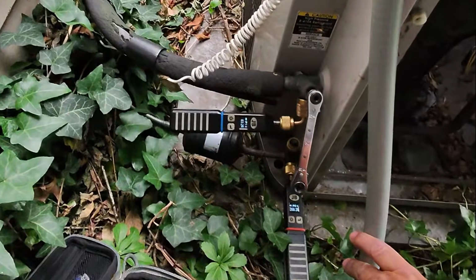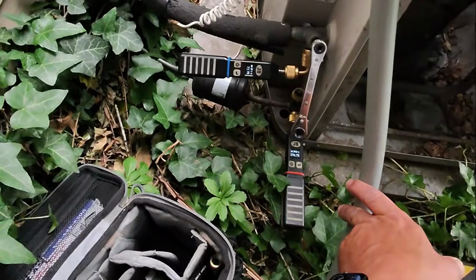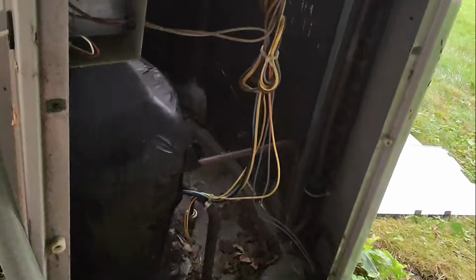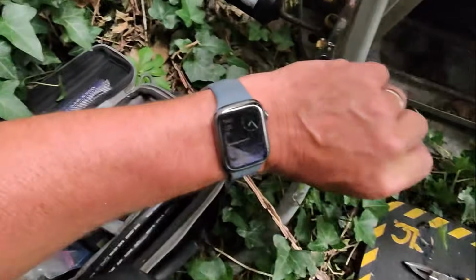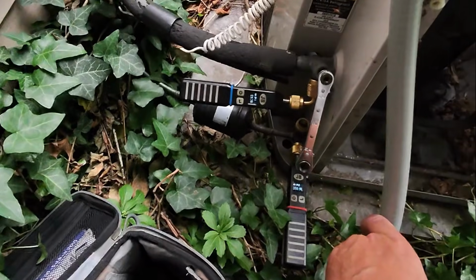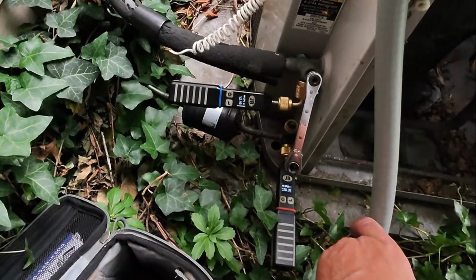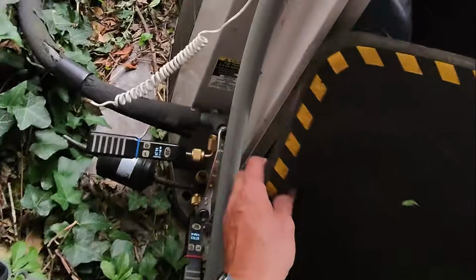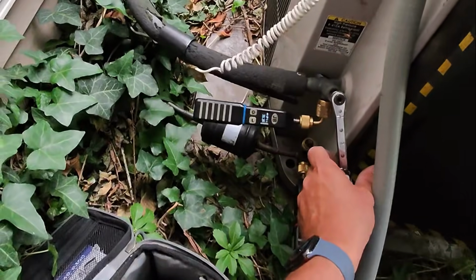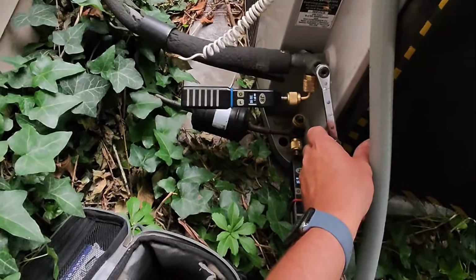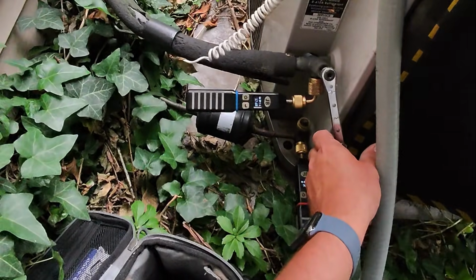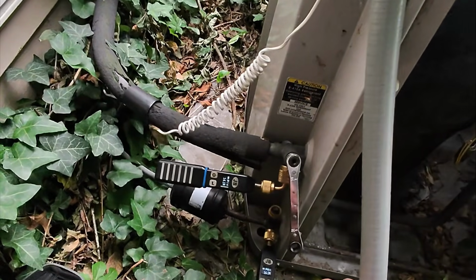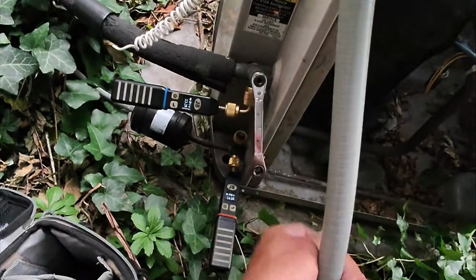We're at 84, 83, 81, 80. If we're lucky, we'll be able to pump all the refrigerant back into the condensing unit, and that'll save us recovery time. It is 7:25 in the morning. 59 psi, 55, 52. We may have a thermal overload issue. 40, 38, 35. That'll do it. 26, 22, 20, 18, 17. Awesome. 14, 13. And see our high side is dropping as well.